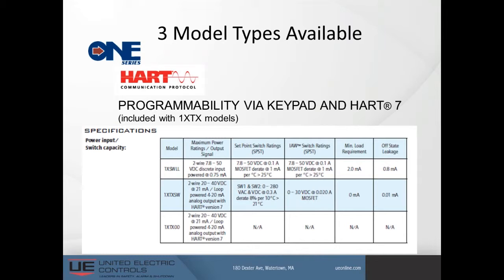So the 3 models that exist today of the 1 Series basically look like what you see on your screen. The very first product is a 1X, and nomenclatures have changed also, but the 1X SWLL is primarily just a switch. It is what the 1 Series platform was designed to do, based on simple switching using the leakage current to power the device. It still exists. It's a 2-wire device, and its power capability is 7.8 to 50 volts DC, a discrete input capability. It has a switch rating of 7.8 to 50 volts DC at 1/10 of an amp.